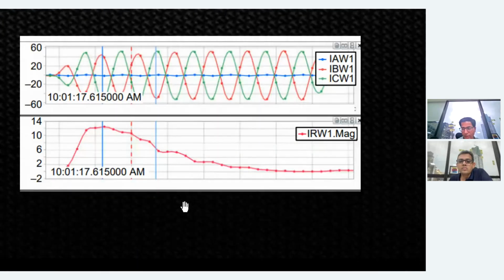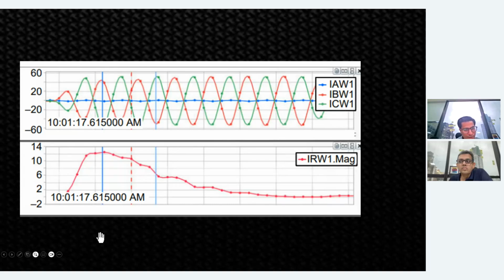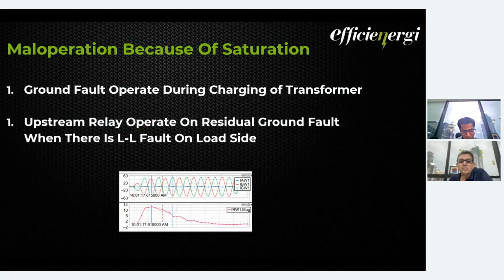So here you can see there is a line-to-line fault, with exactly equal and opposite waveforms in the two lines. But in the residual ground, this much amount of current is seen. This is the RMS value, not a waveform, but it is seen. This is what happens when one of the CTs at this location gets saturated. For this higher fault, one of the upstream CTs gets saturated, and the relay sees it as a ground fault because it is calculated on a residual basis.